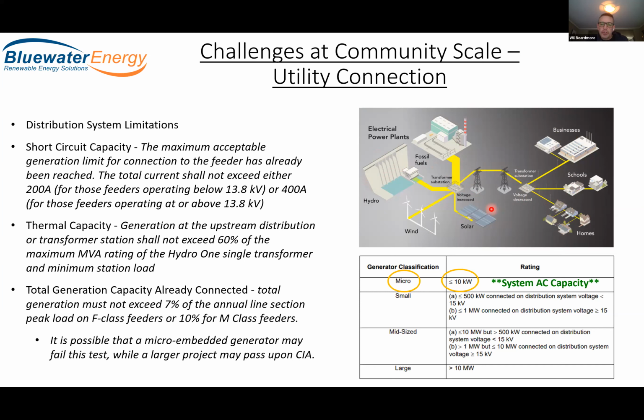Now, as we insert more generation along the distribution line, this model here, electricity was meant to flow one way. And so as we insert distributed generation sources along this line, we're feeding back into the distribution system, and those electrons can possibly flow back the other way. Now we're imposing an effect on the grid that it wasn't necessarily designed to deal with. So there are three limitations. One is called short circuit capacity, one is called thermal capacity, and the other one is the total generation capacity permissible on a feeder.